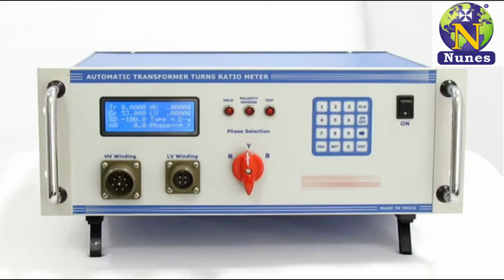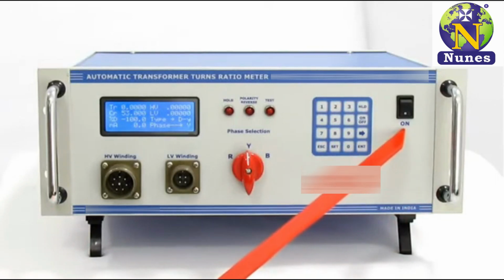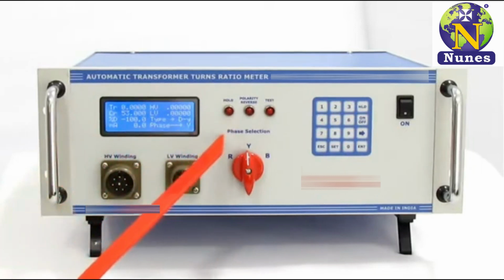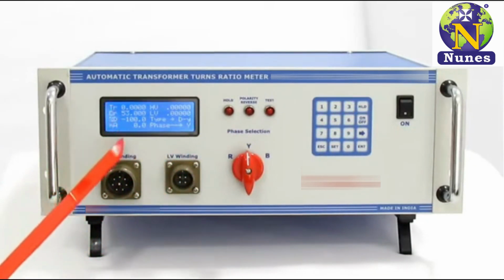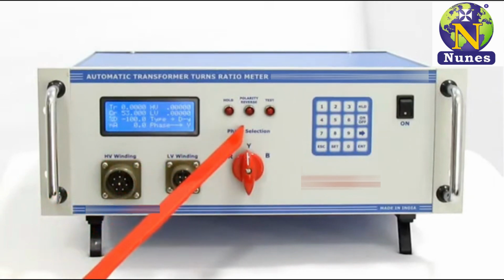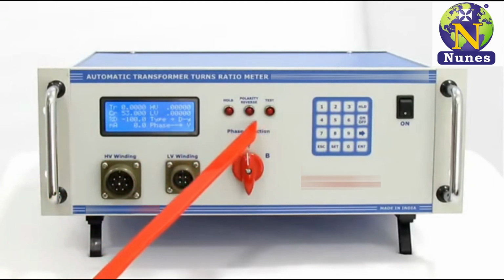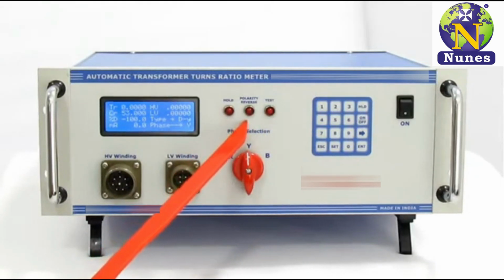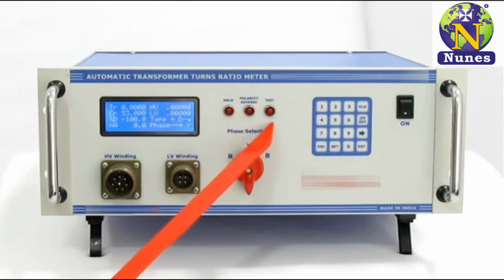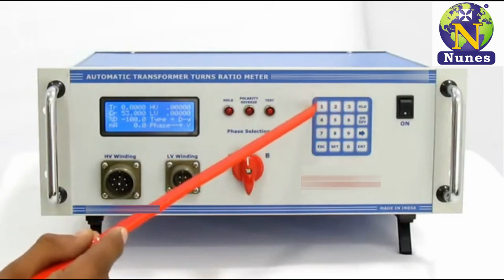Here you can see the front panel of transformer turns ratio meter VTRM. This is the power on off switch. This is a 20x4 LCD display where you can see measuring parameters of VTRM. You can see that 3 indication lamps are provided at the front panel of VTRM. First one is for hold status indication, second one is to show reverse polarity, and third one is for test on indication. This is a 4x4 matrix keypad which has 16 keys.